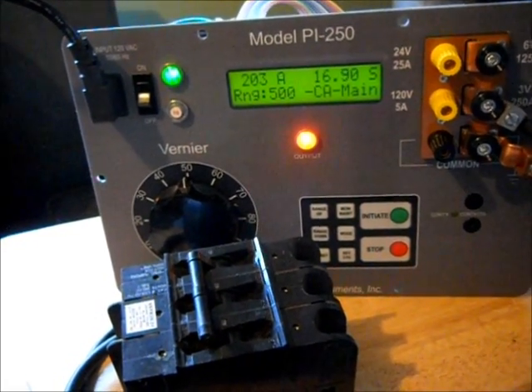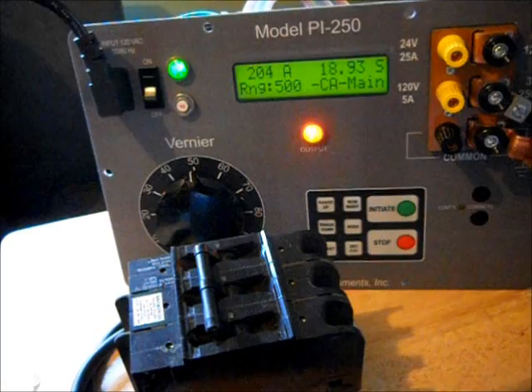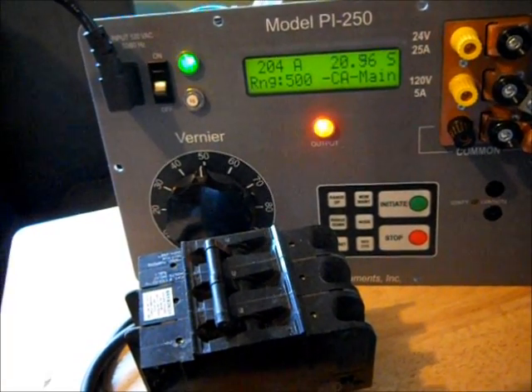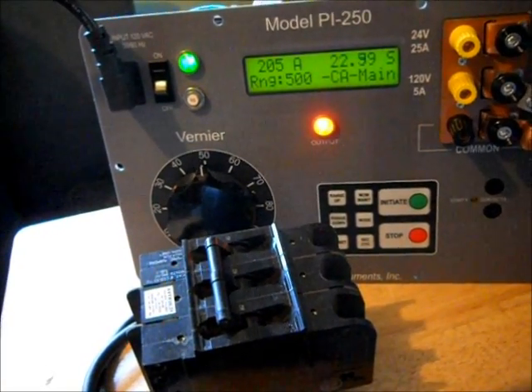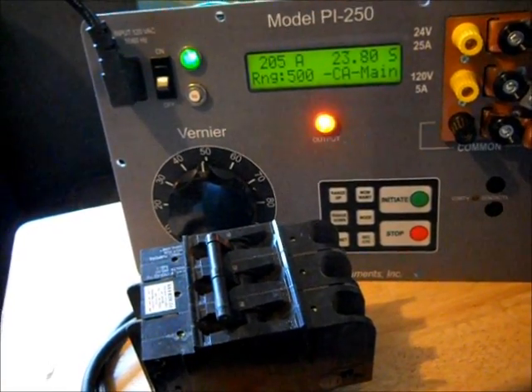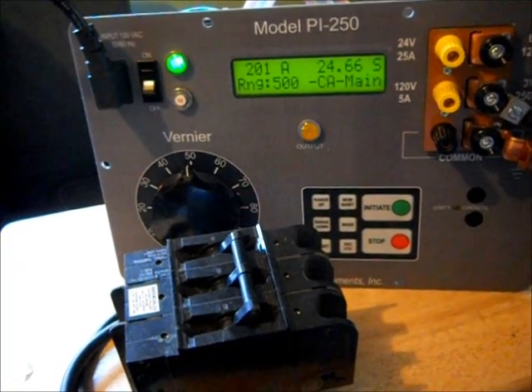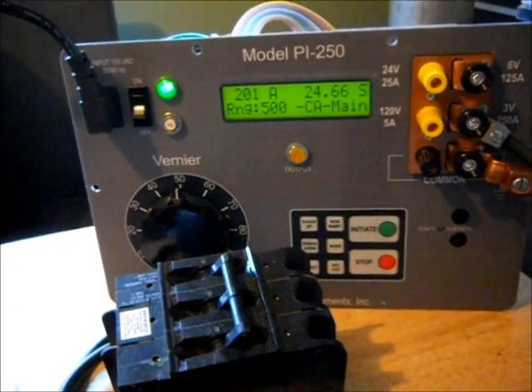Notice it's about 200 amps into a 60 amp breaker, so a little over three times. It should trip probably about 30... okay, 25 seconds. Just about right.